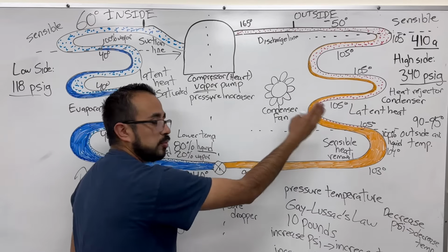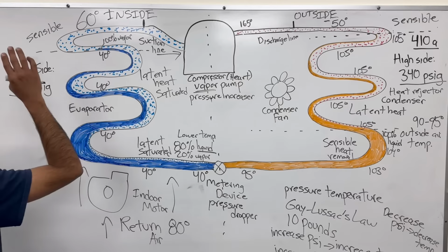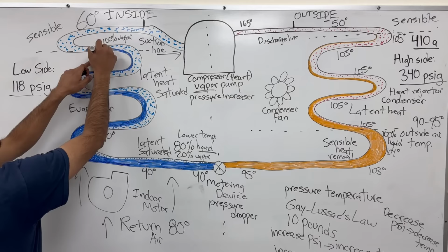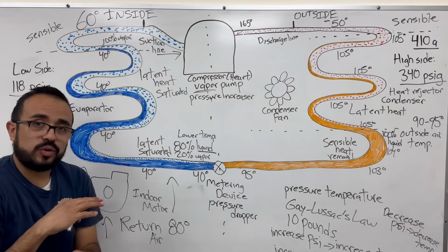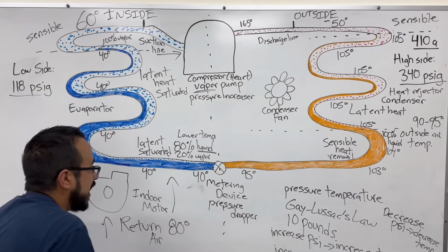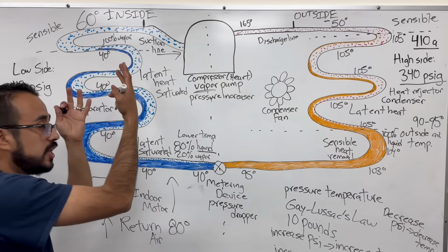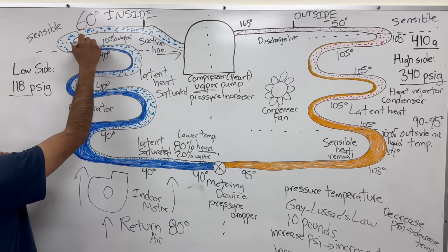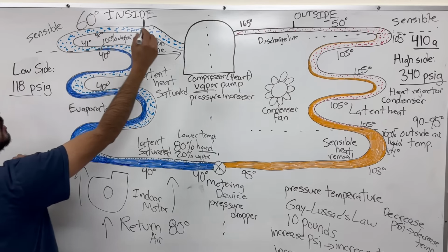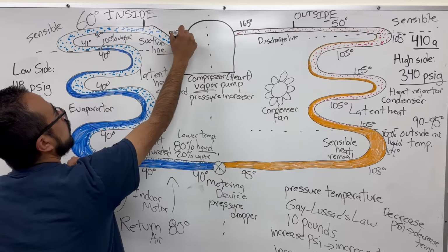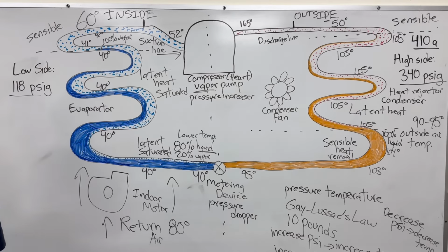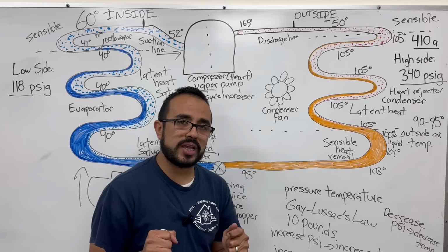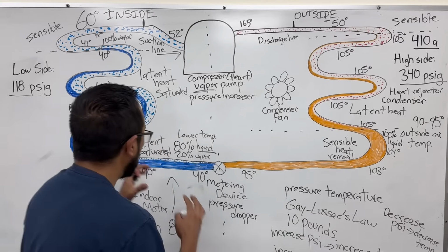Superheat and subcool. But just going back to this right here, right? 100% vapor. When it's 100% vapor, it's already changed states. We're still adding heat, right? We're still adding heat. So because we're adding heat and we've already changed states, 41 degrees, 42, until we get to 52 degrees. 52. But are you starting to understand why heat transfer is so important?